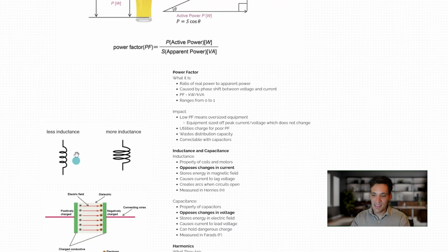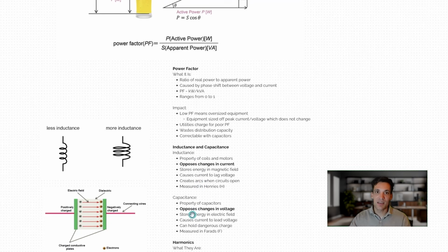So ideally what happens is things like motors and transmission lines generate inductance. Then we need to compensate for this by installing capacitor banks within our system, which you see a lot on renewable energy plants. A lot of renewable energy plants connecting to the grid are actually mandated to install capacitance because power electronics, the inverters that use the DC rectifiers, cause a lot of inductance. So to compensate for this, they're often required to install capacitor banks.